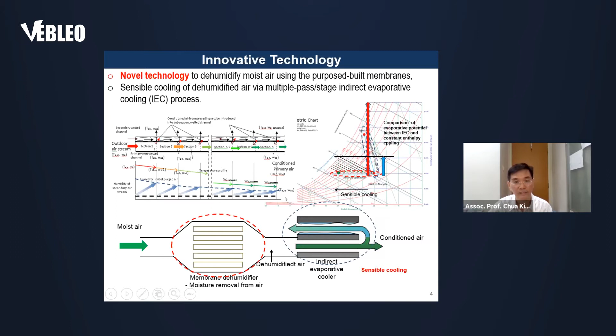And with that, if you look at this very simple animation, we have the membrane. The first stage of the hot and humid air goes through the membrane. The water will be sieved out, and then followed by the second stage, which we call the dew point evaporating cooler. Typically, we take about 15 to 20% of the air that's coming in, and we let it go to the wet channel. As the 15 to 20% of the air goes through the wet channel, it vaporizes the water in the wet channel and cools the adjacent dry channel. So the air will proceed accordingly.